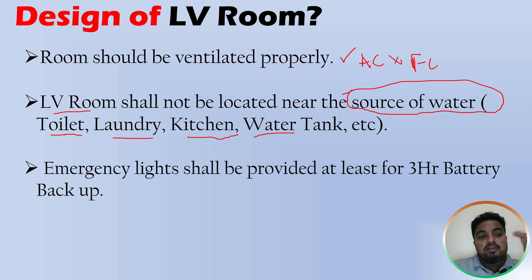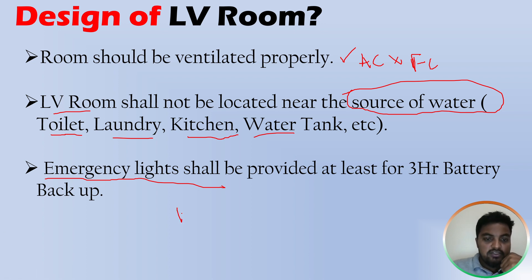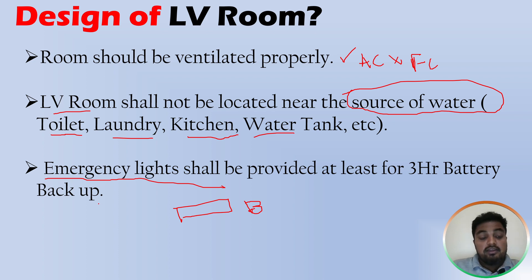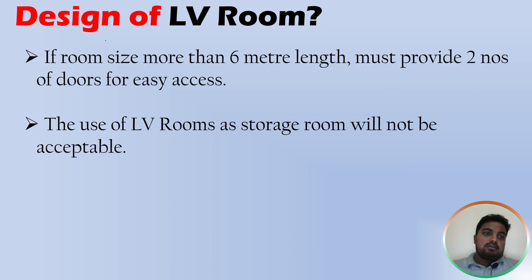The next point: emergency lights shall be provided in the LV room with at least three hours of battery backup. You must provide at least one emergency light inside the LV room with an inbuilt battery for three-hour backup. In any emergency situation, when power is disconnected, this light will remain on for up to three hours.